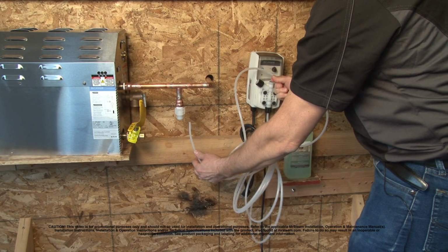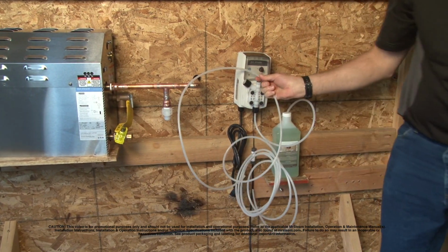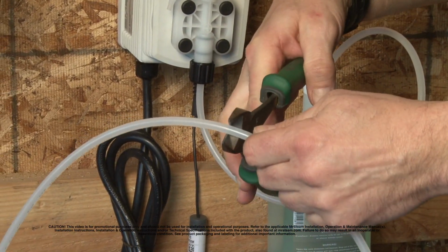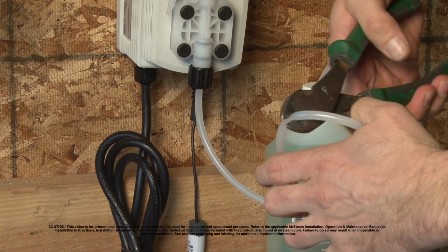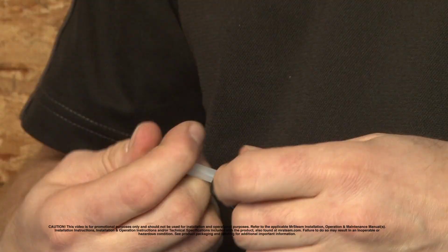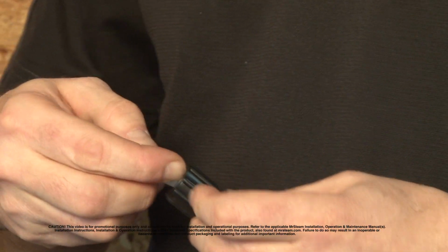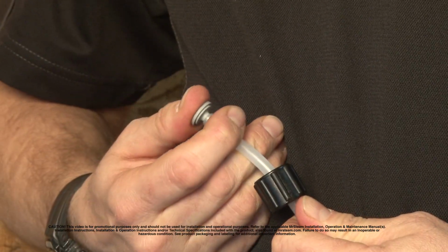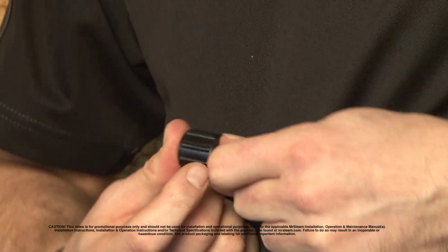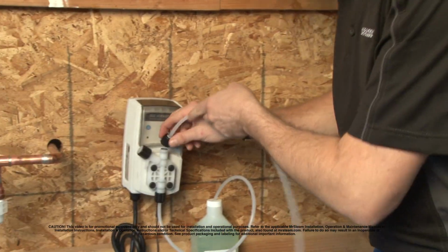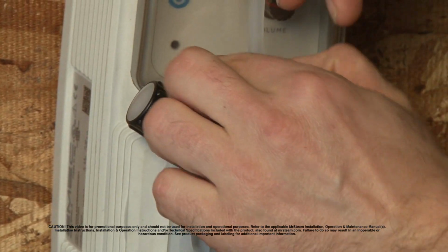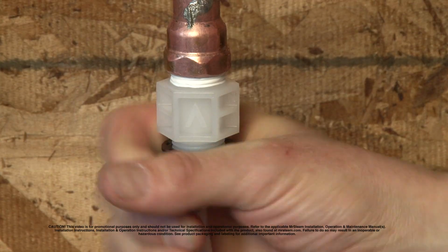Determine the distance between the T-fitting and the pump head, and cut the remainder of this hose to this length. This hose will deliver the oil from your pump head to your steam line. Prepare both ends of this pressure hose in the same manner as the end of the suction hose that goes into the pump head. Now screw one end into the top of the pump head and the other end into the atomizer nozzle.